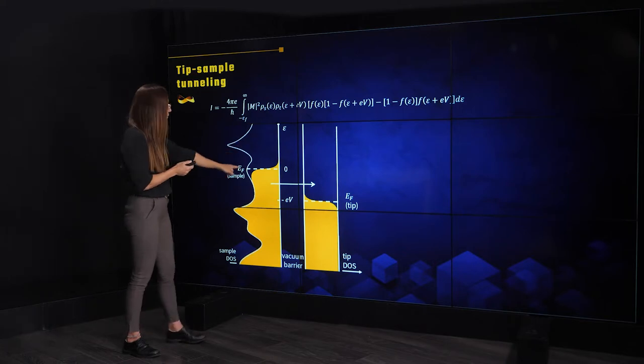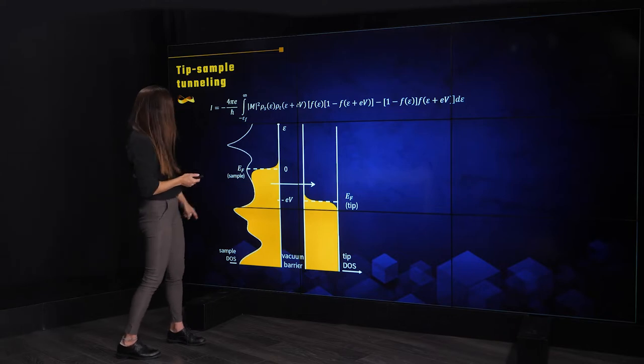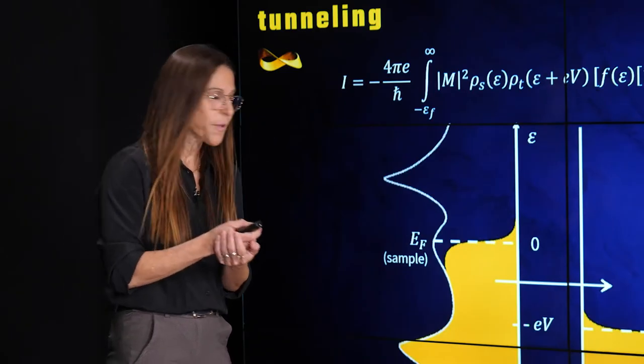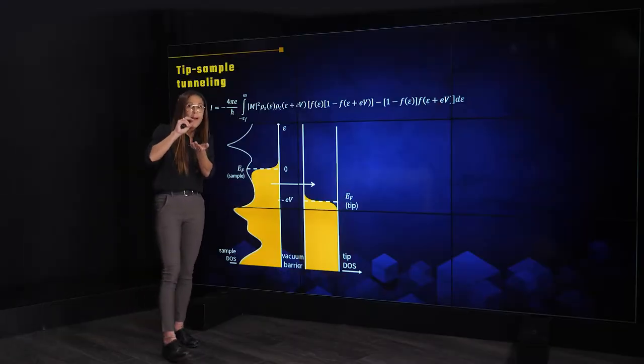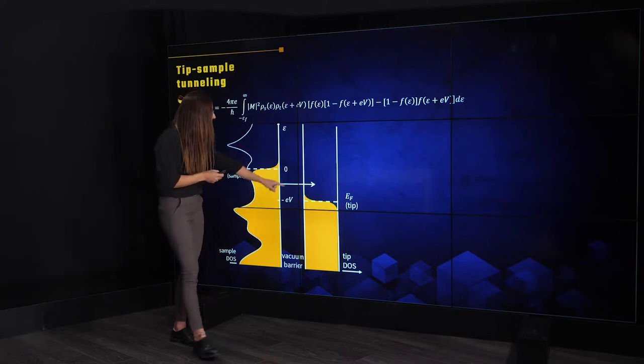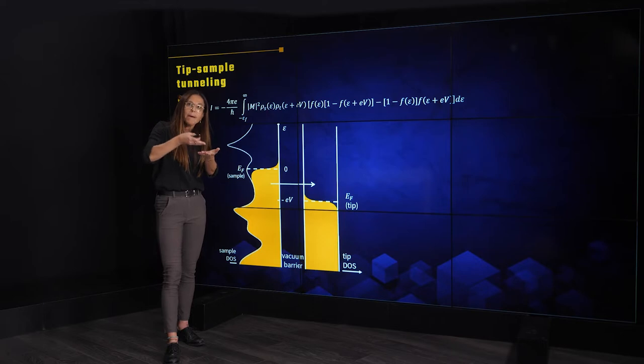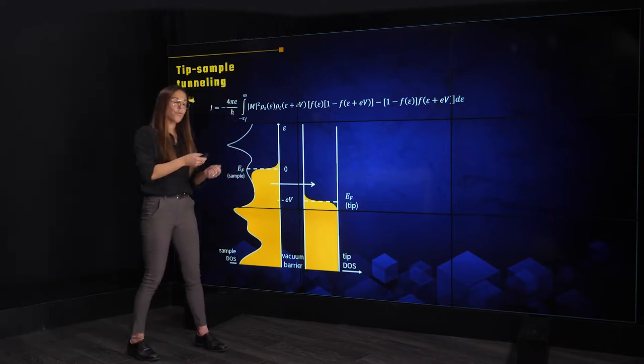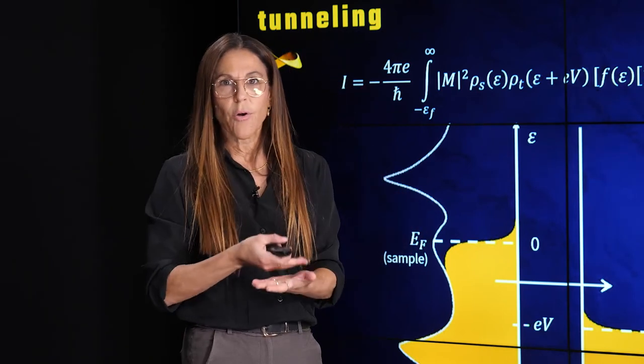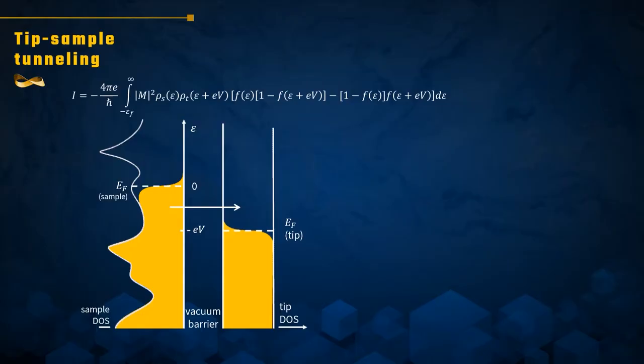Here is an illustration representing the tunneling junction between the tip and the sample. On the left we see the density of states of the sample as a function of energy — this is what we want to measure and explore. In the middle we see the vacuum barrier representing the vacuum distance between the tip and the sample. On the right we have the density of states of the tip as a function of energy, and we see that it is relatively constant, because we pick tip materials whose density of states is constant in the energy region of interest. This helps us to deconvolute the tip's contribution from the tunneling current and retain only information about the density of states of the sample.